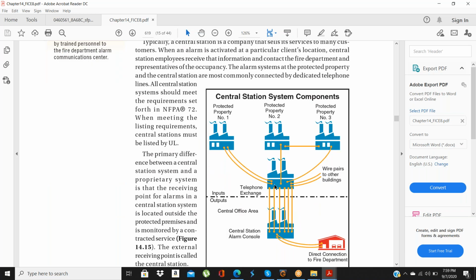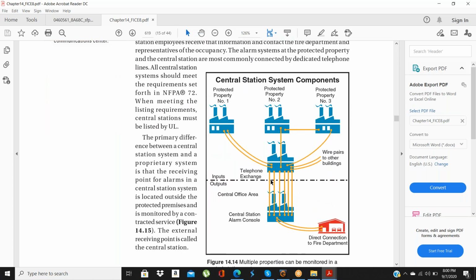In central, all the signals come here, and there is one operator who sees from the screen or device that there's a fire. Then he takes the phone and calls the fire department, giving the property number and address, but he calls the fire department manually by himself. In the remote system, everything is programmed automatically to contact the fire department directly, so the signal isn't coming here, it goes directly to the fire detection system and fire department.